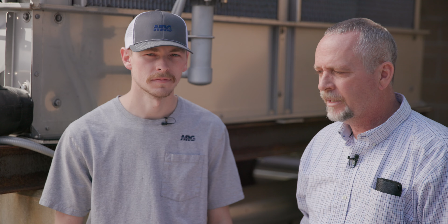Cody, one big thing I've found over the years is these little counterflows are just great towers. They're solid, the price point's good, but they do have their limitations on size. When you start getting into larger applications, big 1,000-ton chillers and up, not that you couldn't still do a counterflow, but it may not be cost effective to go that route. That's where you might want to start looking into a crossflow cooling tower.